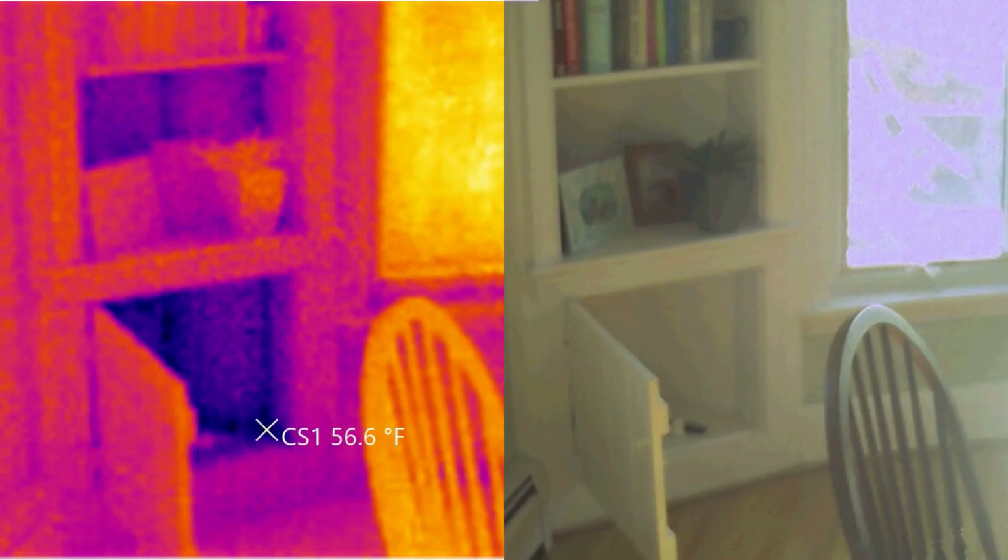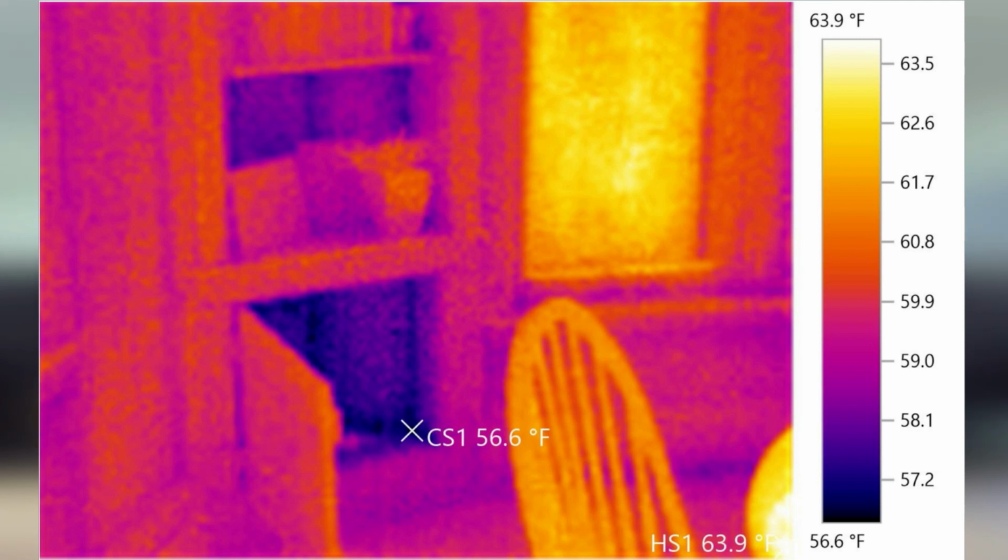So the point here is that ducts are a great opportunity, especially if they're running inside of the envelope, in the attics or garages or basements or crawl spaces, to just make sure that they're sealed, connected, and that everything is working properly, because the HVAC system is designed on pressure. When you have a disconnected duct, not only are you not getting service to whatever duct is disconnected, and leaking air into possibly an unconditioned space, but you're also disrupting the flow to the other supply areas of the house. So everything gets thrown off when you have that type of problem. And the reason why this is so important is, believe me, I see this all too often, and I think it's something that really needs to be focused on.